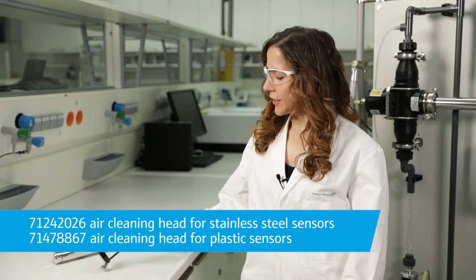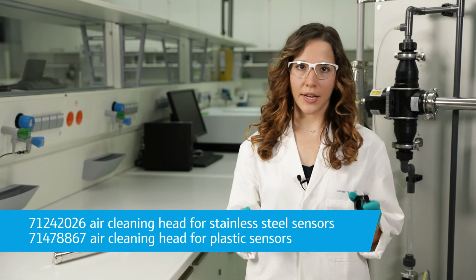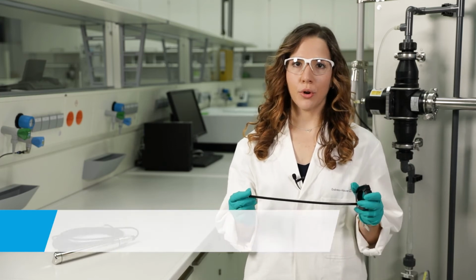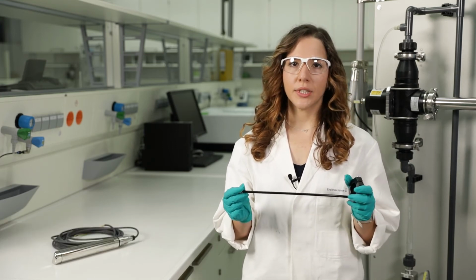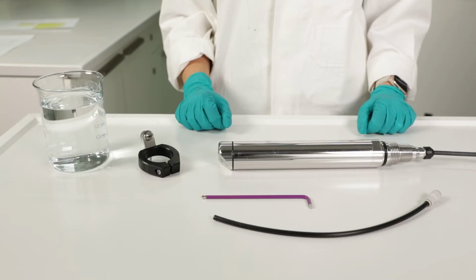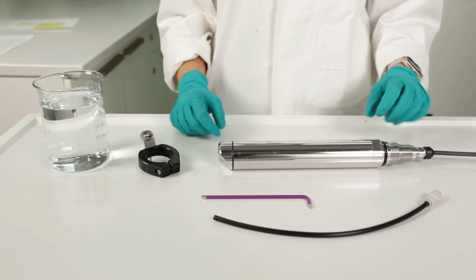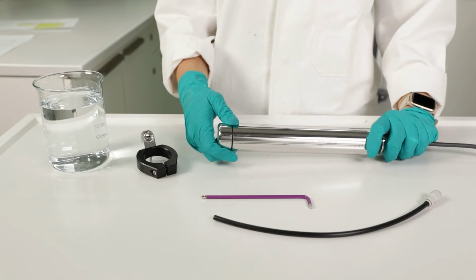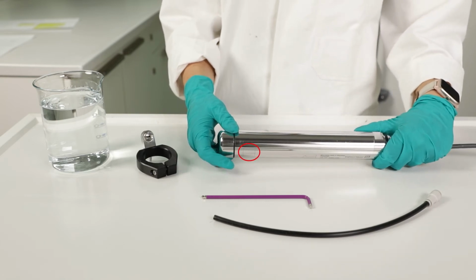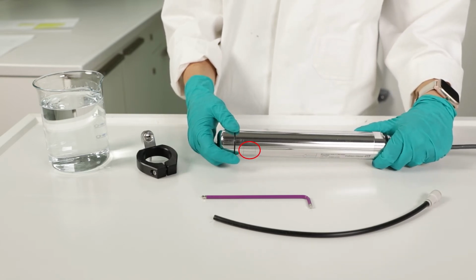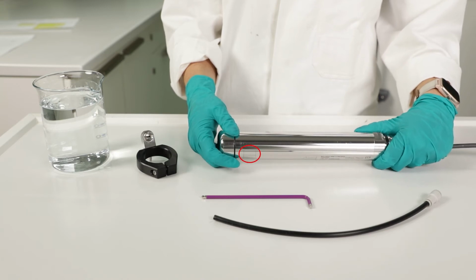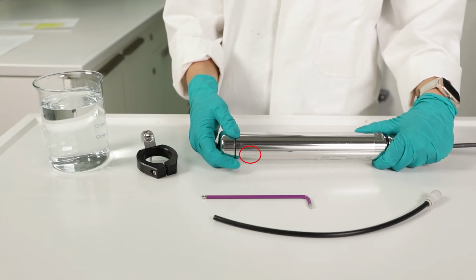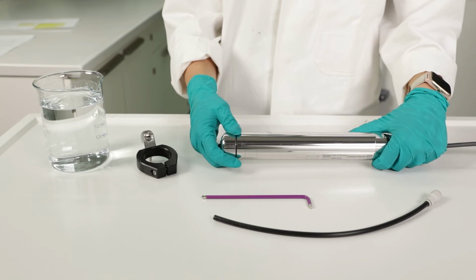For cleaning with air, you need the compressed air cleaning nozzle and, of course, compressed air. For installations in immersion assemblies, there is the compressed air cleaning system. This unit is mounted on the sensor head. The sensor has laser markings on the back of the sensor head, which indicate the correct orientation for best possible cleaning and at the same time simplify the installation, which I will show you now.